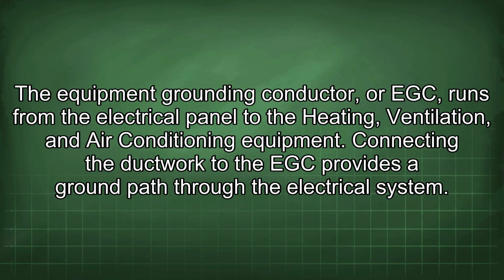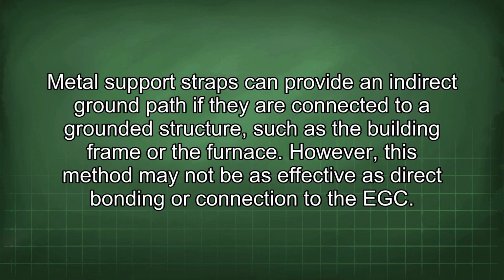The equipment grounding conductor, or EGC, runs from the electrical panel to the heating, ventilation, and air conditioning equipment. Connecting the ductwork to the EGC provides a ground path through the electrical system. Metal support straps can provide an indirect ground path if they are connected to a grounded structure such as the building frame or the furnace. However, this method may not be as effective as direct bonding or connection to the EGC.